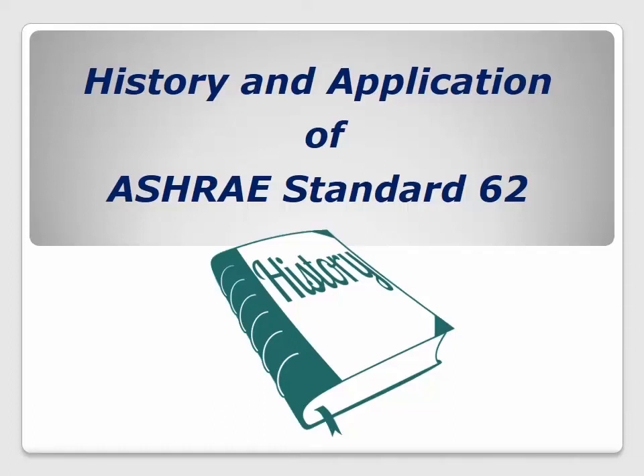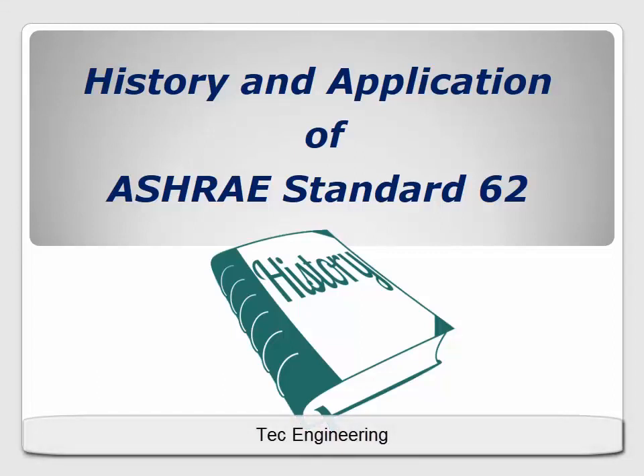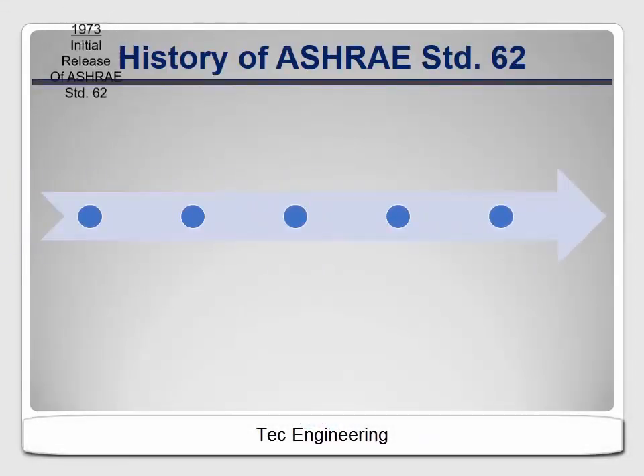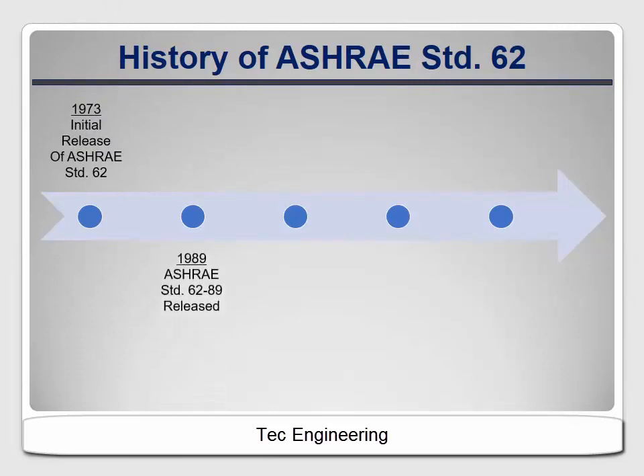Before we get into the technical details of ASHRAE Standard 62 in the upcoming lessons, it'll be helpful to first understand the history of this standard as well as its use in common residential construction applications. ASHRAE Standard 62 was originally released in 1973. In 1989, a version was released that included a recommendation of air exchange rates of at least 0.35 air changes per hour or 15 CFM per occupant.